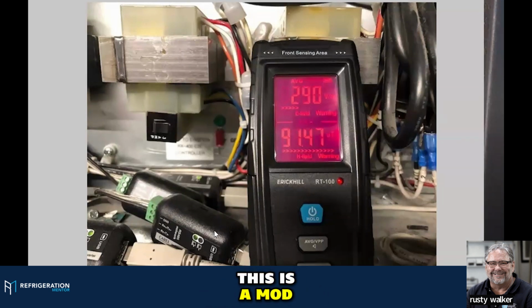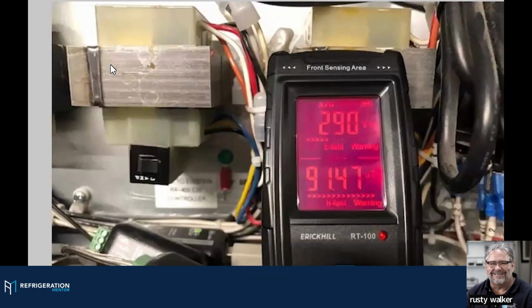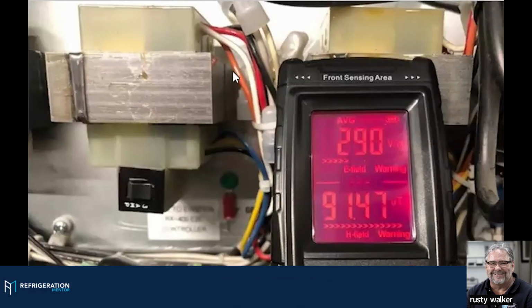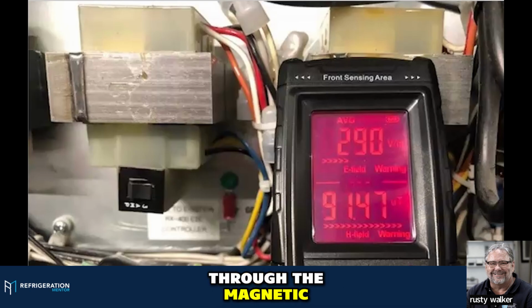This is a Modbus to USB converter, and they keep dropping these things offline. Nobody can figure out why. What do you see right here? One, two, and there's two more. They ran it by the transformer. Transformers are hit up with magnetic induction, magnetic fields, so they're running straight through the magnetic field.